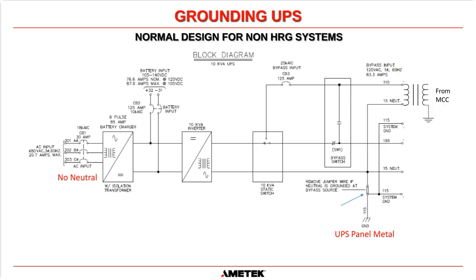Okay, but that's not what we recommend. What we always recommend is that this is going to be a transformer that's located relatively close to the UPS in most circumstances. Okay, so what we always recommend is that the plant tie the secondary neutral of that bypass transformer to ground within the transformer itself.